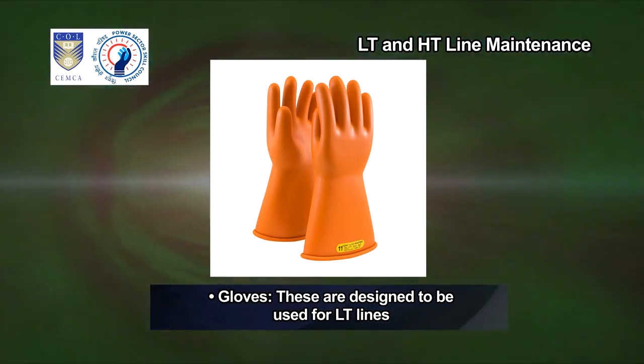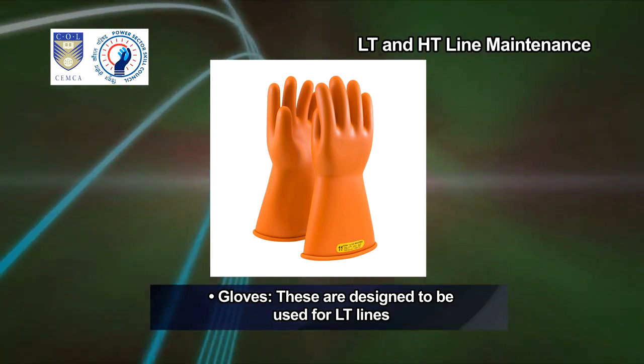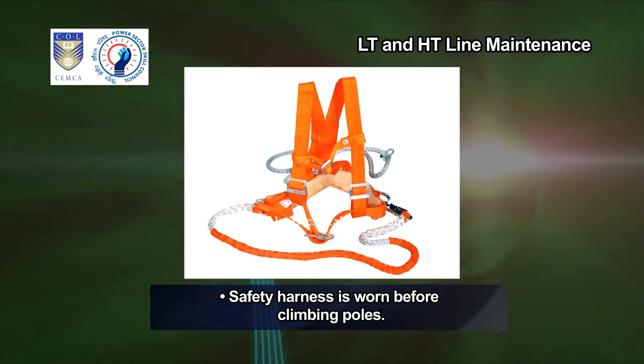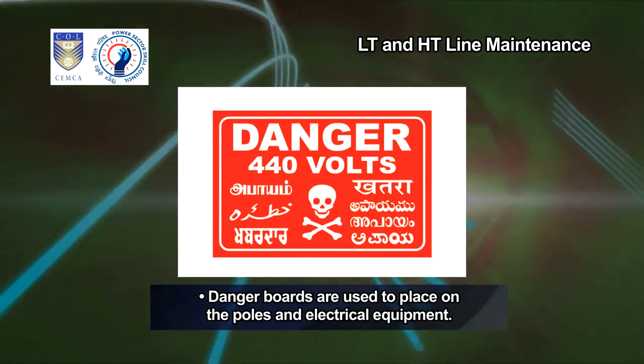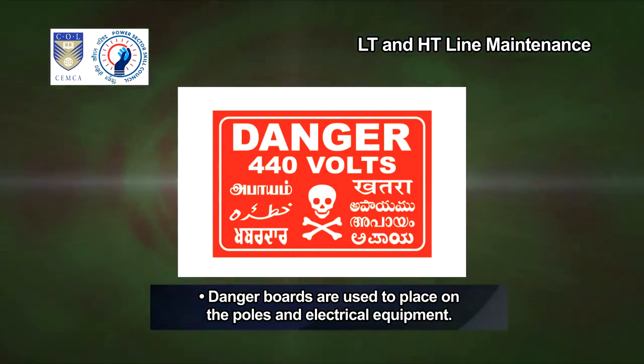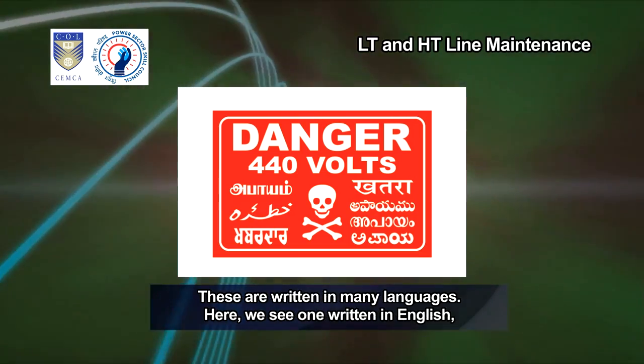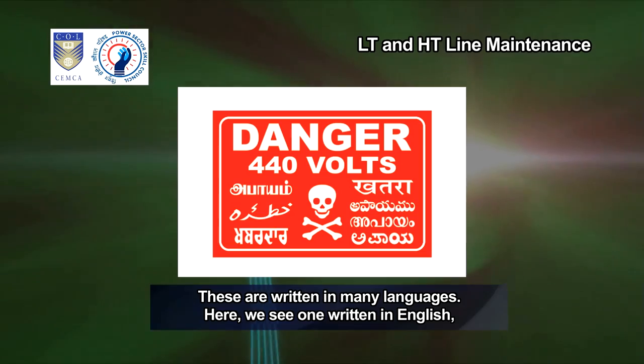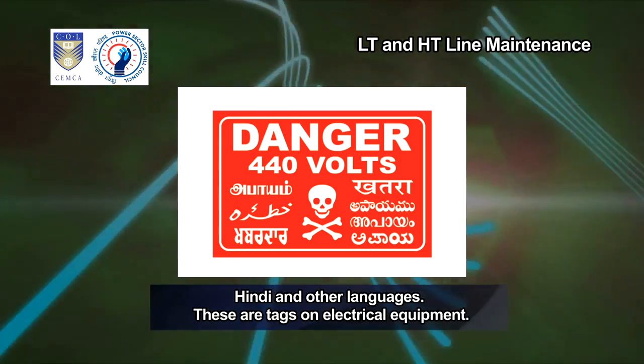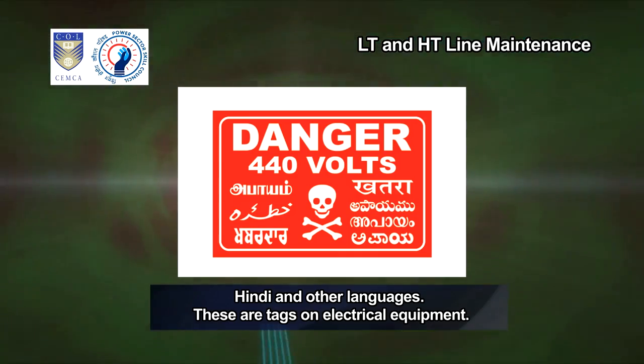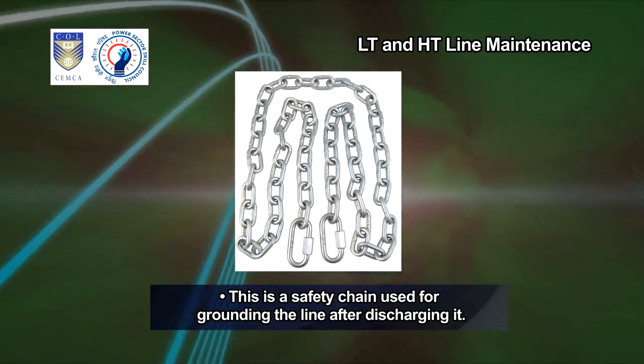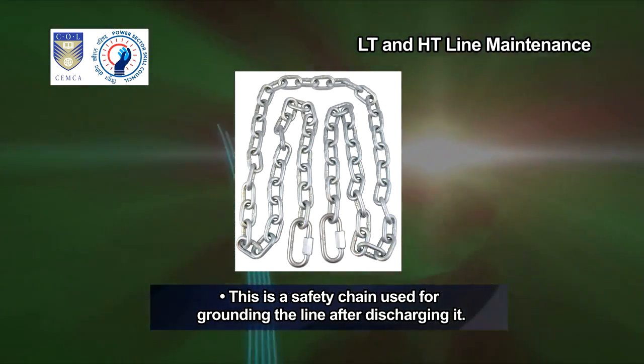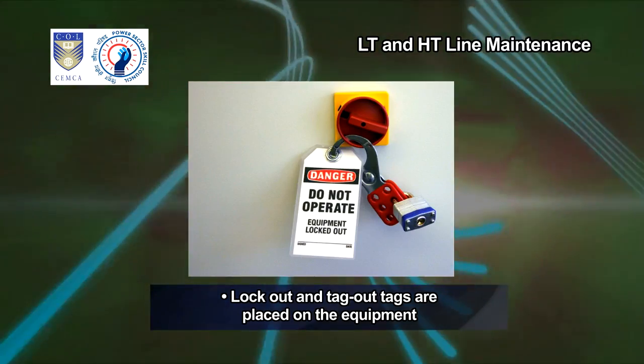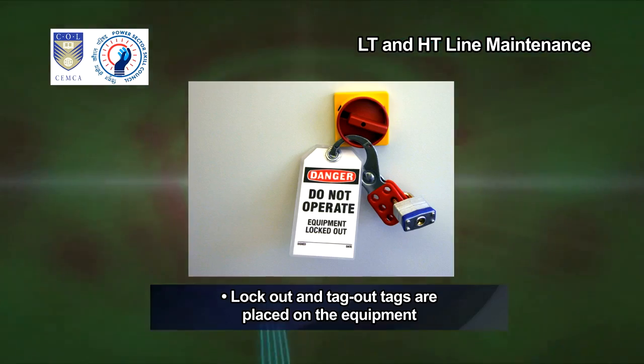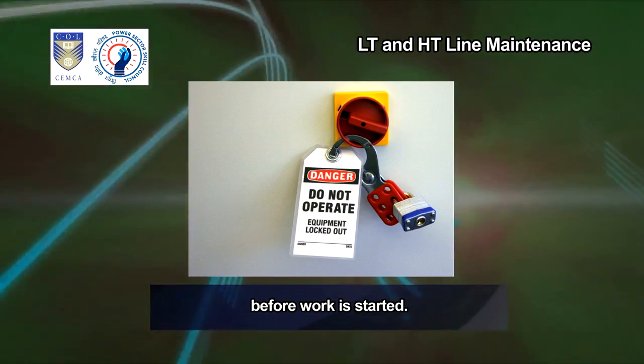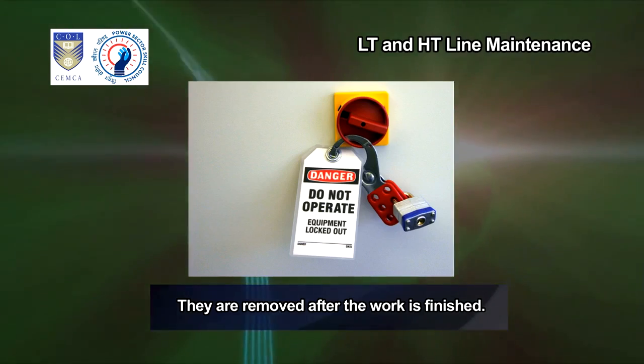Gloves. These are designed to be used for LT lines. Safety harness is worn before climbing poles. Danger boards are used to place on the poles and electrical equipment. These are written in many languages. Here we see one written in English, Hindi and other languages. These are tags on electrical equipment. This is a safety chain used for grounding the line after discharging it. Lockout and tag-out tags are placed on the equipment before work is started. They are removed after the work is finished.